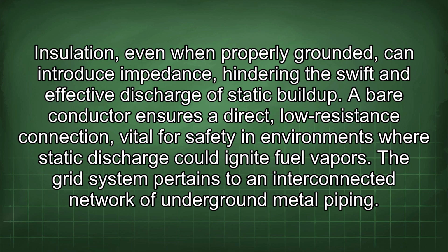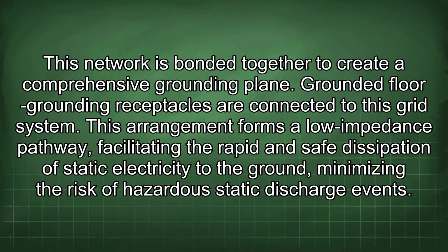The grid system pertains to an interconnected network of underground metal piping. This network is bonded together to create a comprehensive grounding plane. Grounded floor grounding receptacles are connected to this grid system. This arrangement forms a low-impedance pathway, facilitating the rapid and safe dissipation of static electricity to the ground, minimizing the risk of hazardous static discharge events.